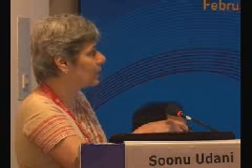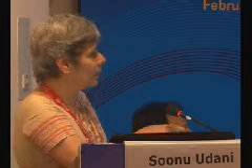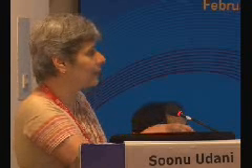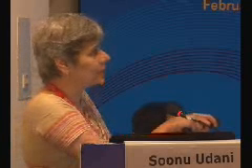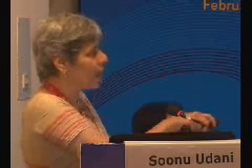The important thing about this mode is, with pressure control, when you set a pressure limit, your volume will definitely go down if your compliance goes down. Here, if you set a pressure limit, your pressure will go up, if your compliance goes down, till your volume target is met. But it will not go beyond your pressure limit. And therefore, at least you will be able to maintain your targeted volume.